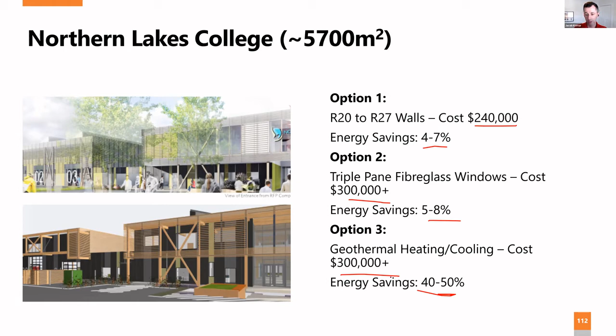The point is that building upgrades aren't always the same. Some give you way more bang for buck. And geo is one of the high ones. The best one I would say is energy recovery on the fresh air. That's still one of your lowest hanging fruit. So for 40 grand, we reduce the heating energy by 20 to 40%. We always recommend first putting money into energy recovery, even before a geo system.